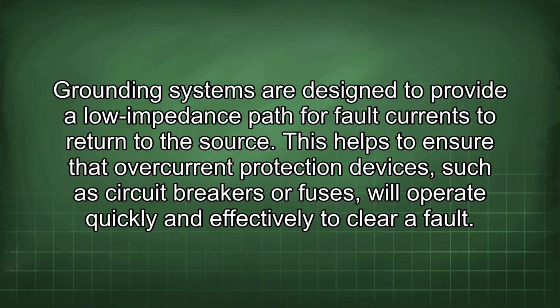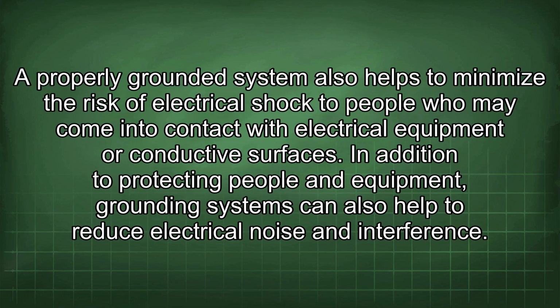Grounding systems are designed to provide a low-impedance path for fault currents to return to the source. This helps to ensure that overcurrent protection devices, such as circuit breakers or fuses, will operate quickly and effectively to clear a fault. A properly grounded system also helps to minimize the risk of electrical shock to people who may come into contact with electrical equipment or conductive surfaces.